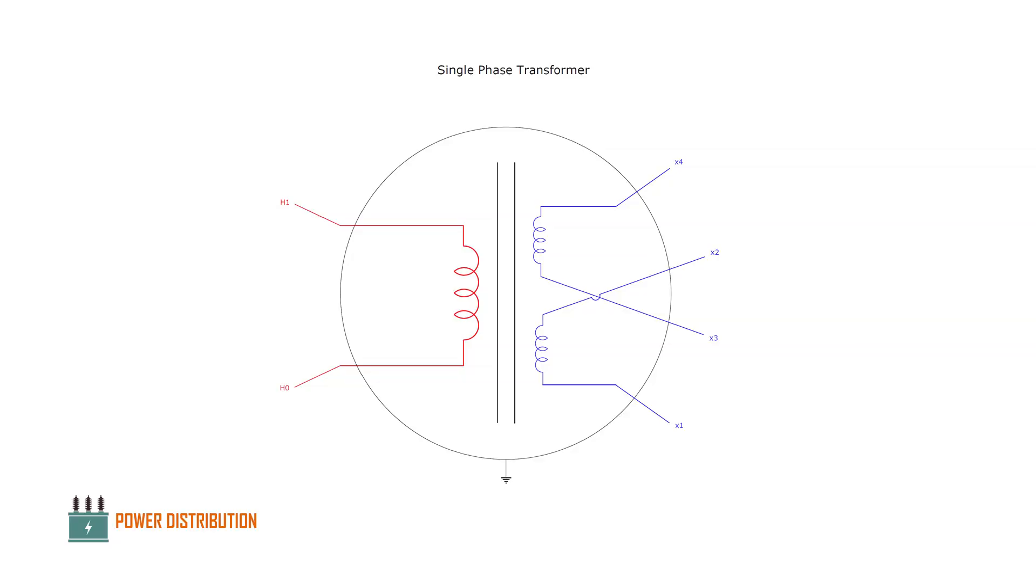Here I draw the schematic for a clearer view. As you can see, for our purpose which is insulation testing, we can view that in this transformer there are three coils we are going to measure. Since in the secondary windings there are two coils which are independent, we will measure both of these windings separately.